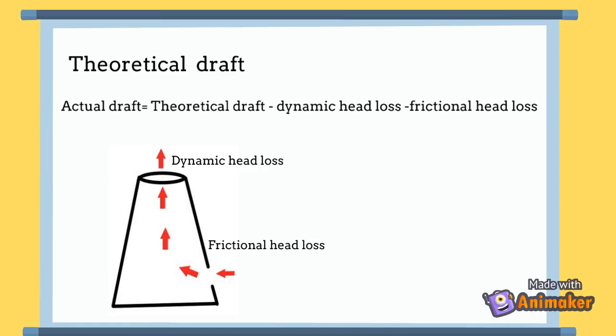It should be noted that the draft calculated was a theoretical draft. In an actual chimney, there is dynamic head loss due to the sudden exit of the flue gases, and also frictional head loss along the walls of the chimney. So the actual draft equals theoretical draft minus the dynamic head loss minus the frictional head loss. Therefore, the theoretical draft is always greater than the actual draft obtained through a chimney.